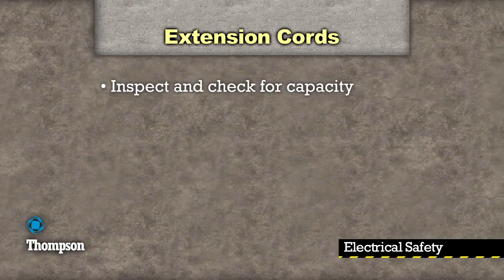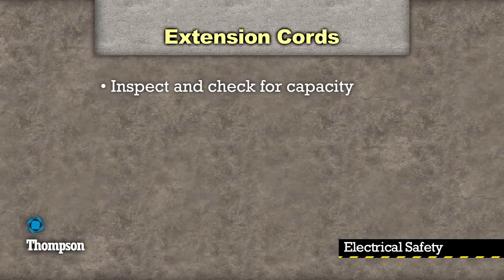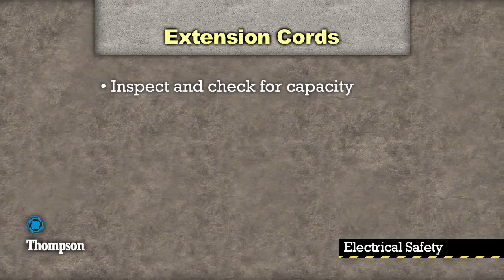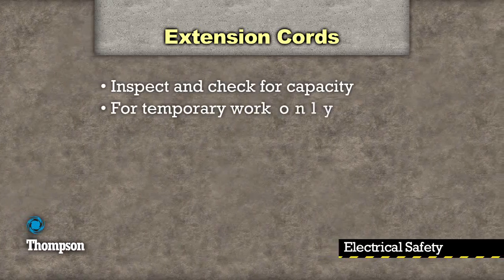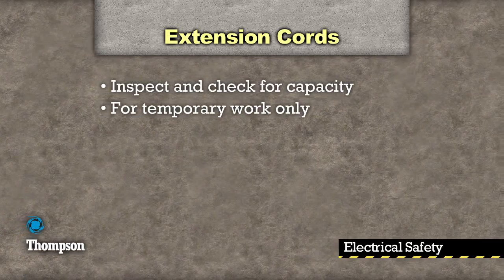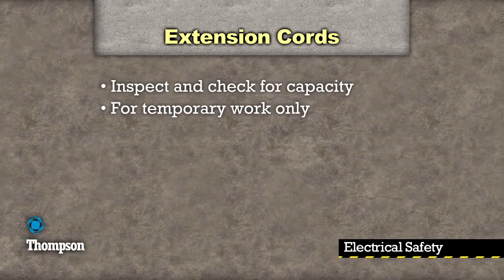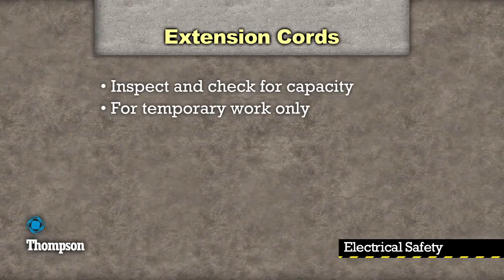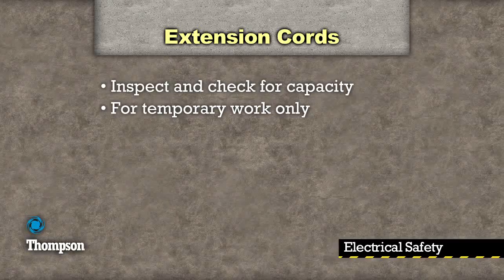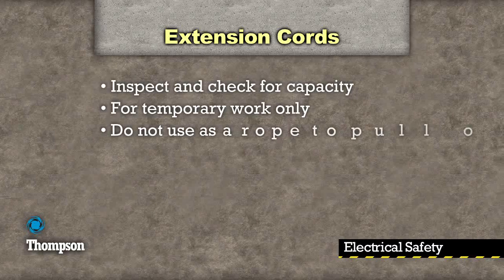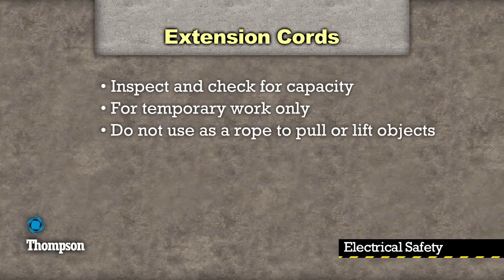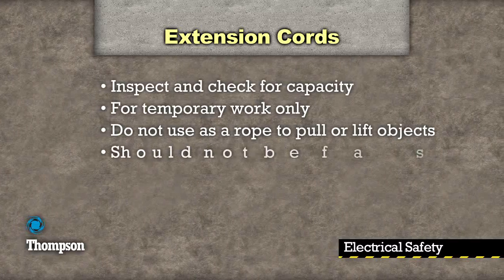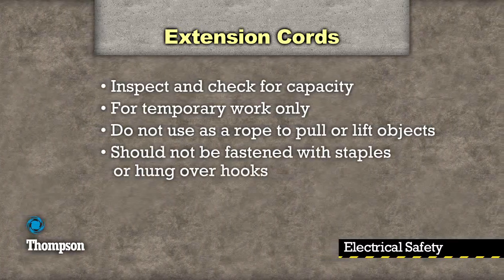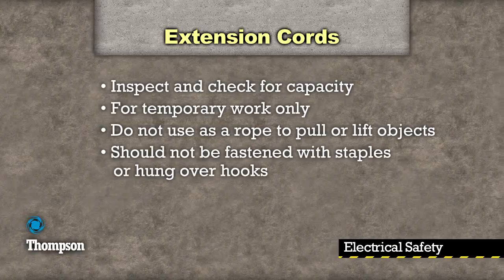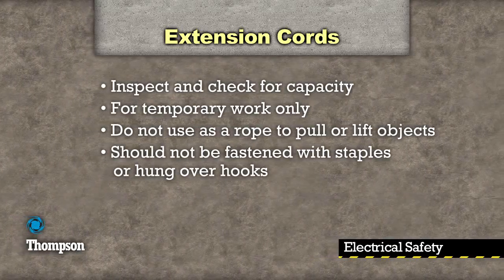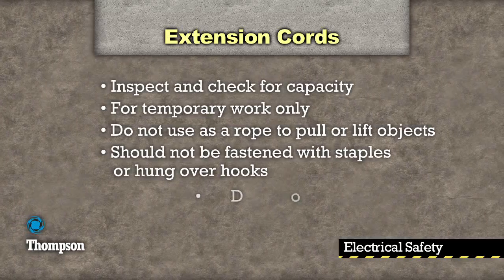Is the extension cord rated for outdoor use? If not, the cord could overheat, start a fire, or trip a circuit breaker. Remember, extension cords are designed only for temporary work. They are not intended to be used as a permanent power source because they're more likely to be damaged or overloaded, and they're not supplied with their own circuit breaker as a hardwired system would be. Extension cords are not ropes. They can easily be stretched and damaged if used to hoist objects. Do not use staples or nails to hang extension cords because this could cause damage to the outer jacket insulation. If the wire becomes exposed, the current could reach ground through the nail or staple and cause a short-circuited and hot cord.